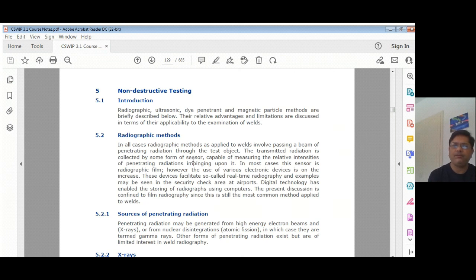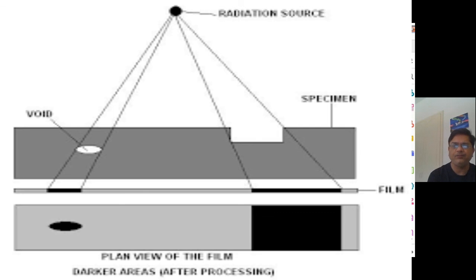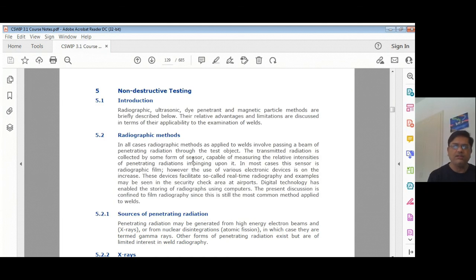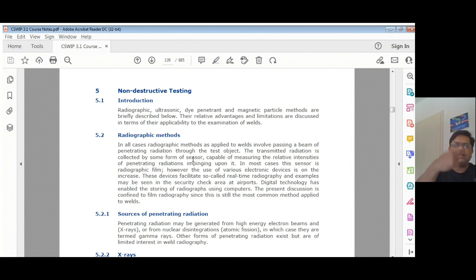So in all cases, the radiographic method as applied to the weld involves passing a beam of penetrating radiation through the test object. So what happens is there is a camera. Attached to the camera on both sides, there is a wire or a cable, let's say, and this cable is a hollow cable. One end of the cable is just 1.52 meters long. That cable will go on the test piece. Let's say, as you see in the photograph, it will either be a plate or a pipe. It will go there and you have to put an elastic there so that it will stay there. It should not shake at all.